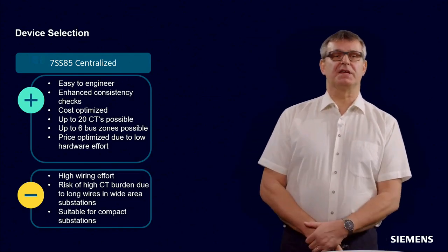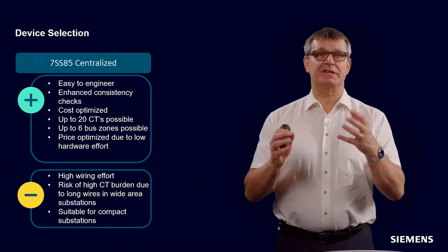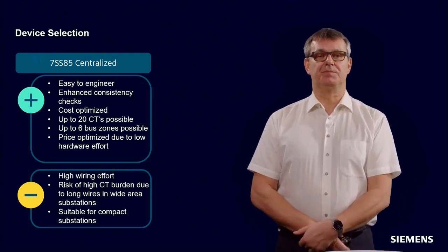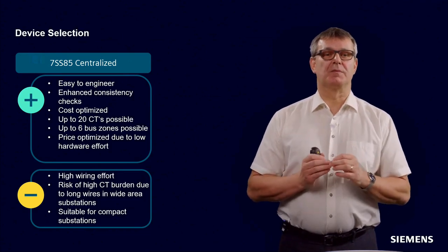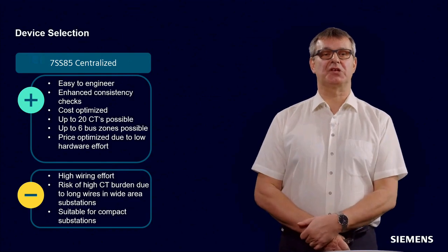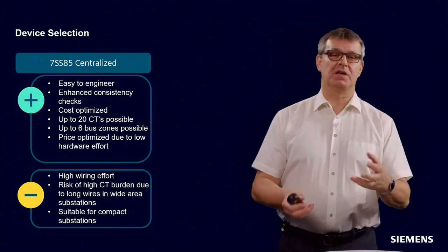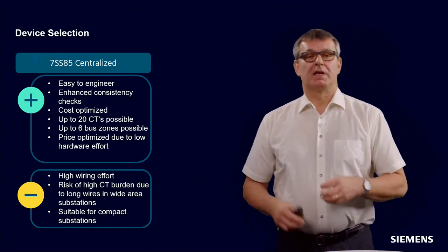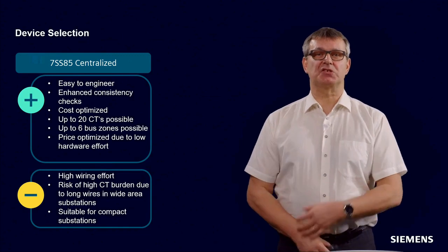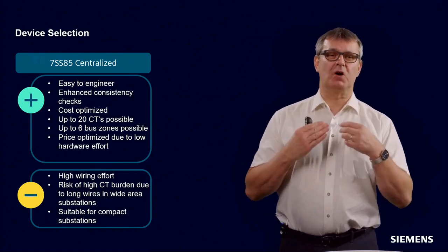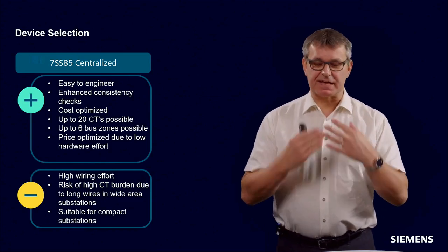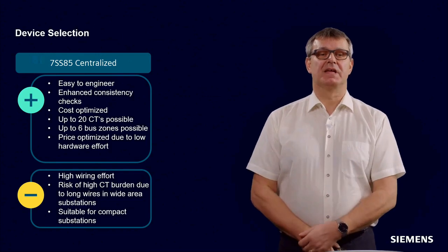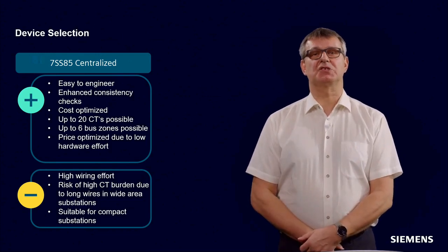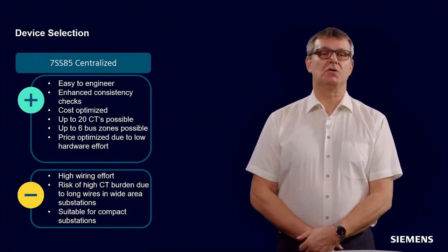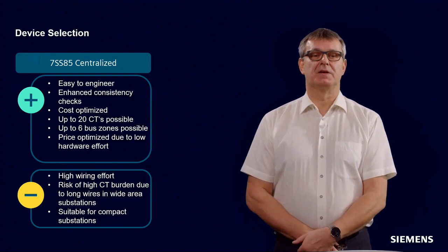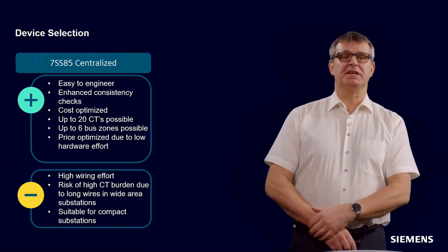Let's start with the centralized busbar protection, the 7SS85 Thunderbird. What are the advantages? It's very easy to engineer. DIGSI 5 during this engineering brings us really enhanced consistency checks. So it will be nearly impossible to bring a wrong configuration to your device. As it is a centralized busbar protection, you have only one device, only one CPU instead of several CPUs, instead of several devices. It's cost optimized. So centralized busbar protection is mostly, in each case, also the best one in case of price. Up to 20 CTs are possible.